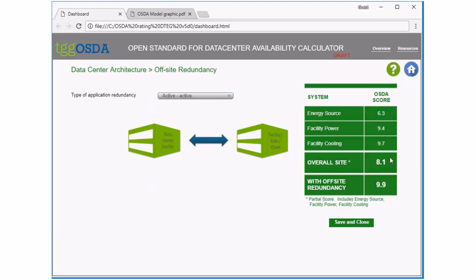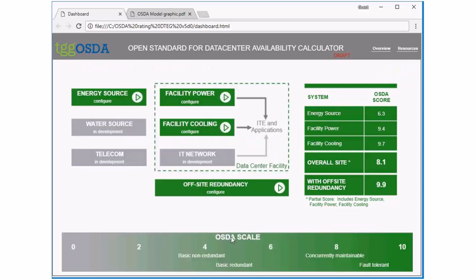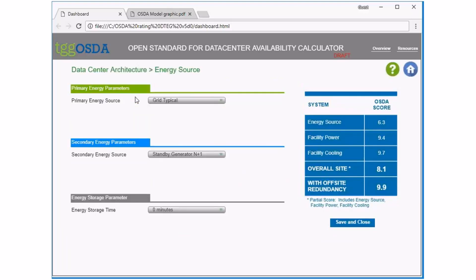The last module you can alter is off-site redundancy. This is a simple way to look at what happens if you have an application that can take advantage of multiple sites — whether it's running concurrently in the cloud or at another site. That application score is the 9.9 shown here; if you have two sites each scoring 8.1, the combined score would be 9.9 in active-active mode. Select none and it removes it. This is mainly for demonstration purposes because we're not currently modeling the telecom and IT network, so the design of those systems is not taken into account in that number.